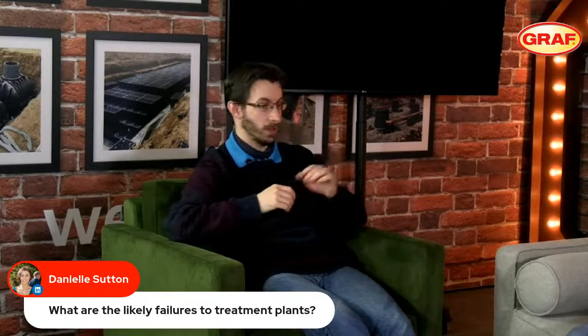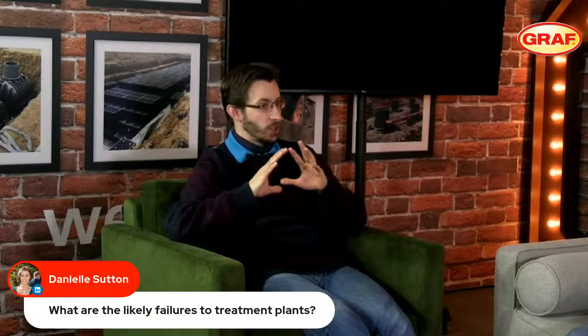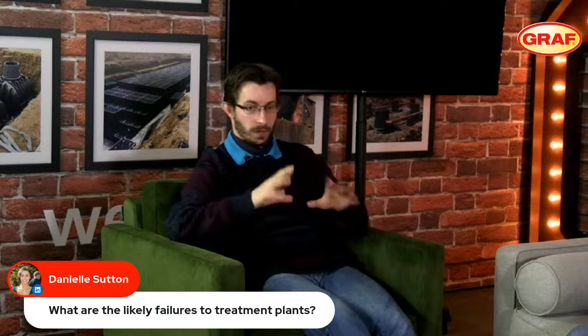You may need to change the air filter. If it's a piston or a diaphragm compressor, that needs to basically just be taken out and just washed and then put back in again. If it's a rotary vane compressor, you need to take the blades out and replace them every 3,000 working hours. So there's a bit of understanding and appreciation that needs to be taken into consideration of the working components.